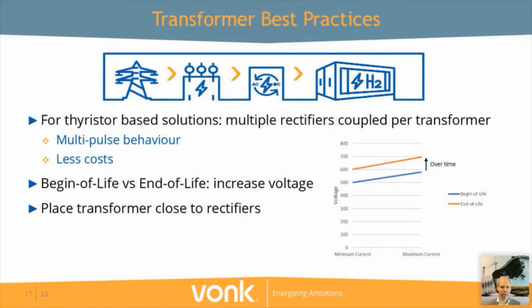From the power factor compensation, we go to the transformer. This is an item in which we have a generic approach, and we're not looking into differences between different application environments. We've got a number of best practices from experience, and the first one that I would like to zoom into is that of applying multiple rectifiers per transformer, especially for thyristor-based solutions.